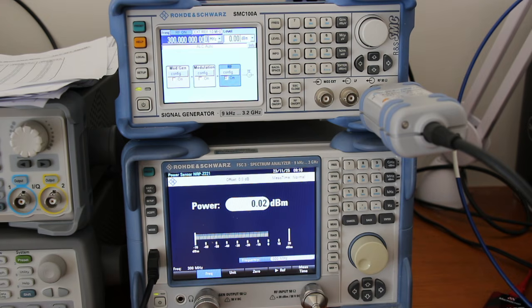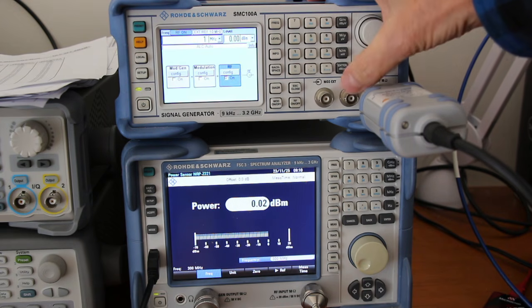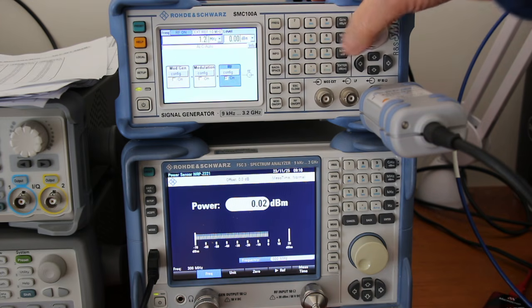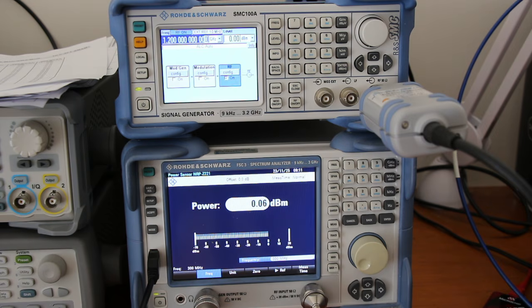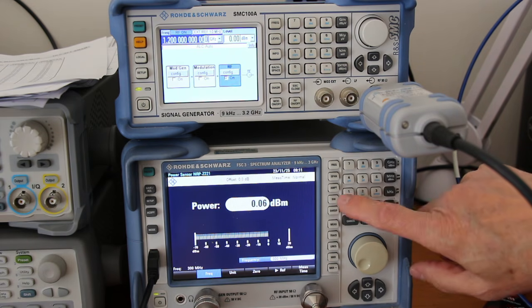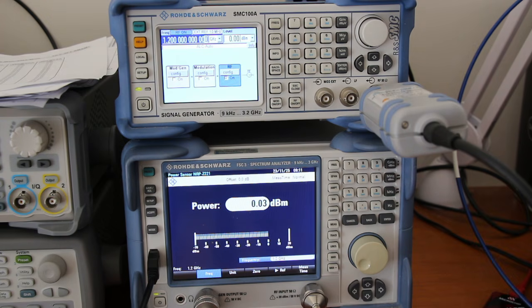To test the BW of the scopes, I'm going to use my trustworthy generator from Rohde & Schwarz and a power meter of the same manufacturer. So let's check the quality of this generator. I set 300 megahertz here, 0 dBm, and you can see down here, practically spot on. Now let me change the frequency to 1.2 gigahertz, and you see that the level is practically the same.